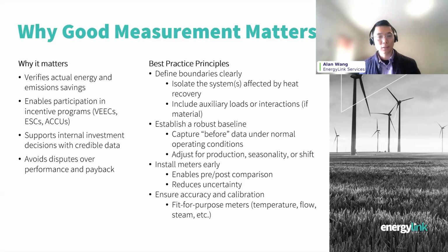You want to isolate only the systems affected by the heat recovery project, but you don't want the boundary to be too big or cover too many things, because the verified savings will then maybe be insignificant within the boundary. It will then be difficult to verify what the real saving is, and it also adds uncertainty to the savings accuracy. We'll discuss this a bit more in detail in the case study later.